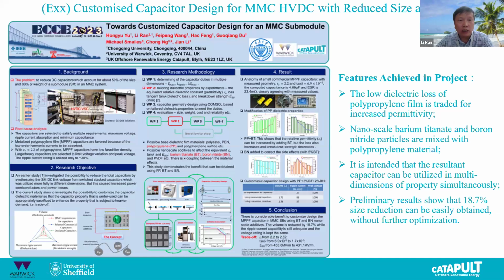Right. This was an adventurous project about capacitors in the MMC system and MMC submodule, and the capacitors occupy at least 50% of the volume and maybe more than 50% of the weight. And in offshore conditions, the size and the weight are both very important factors, so we want to reduce them. And the idea was to explore, to optimize the capacitor dielectric material so that under the MMC converter conditions, the properties of the capacitors in multiple dimensions are utilized towards the limits almost simultaneously.